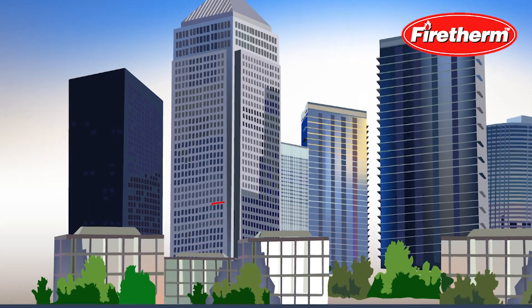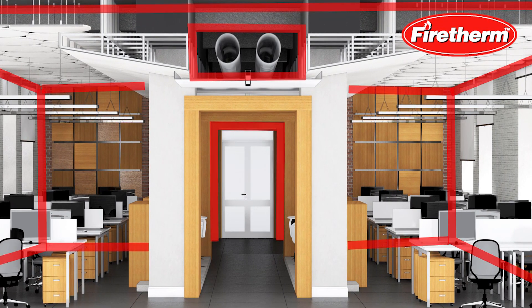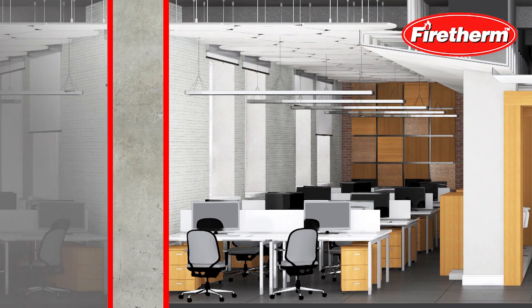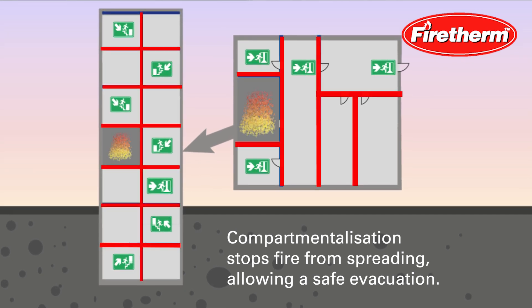National Building Codes are written in such a way that it's important to prevent the growth of fire by compartmentation. Compartmentation limits the extent that the fire can spread, and therefore allows people to escape, and when the emergency services attend site, to help them to finish out the evacuation, and also to fight the fire.